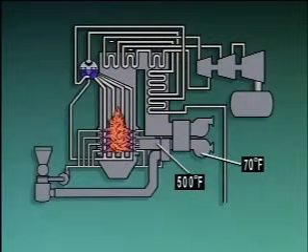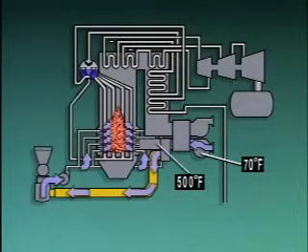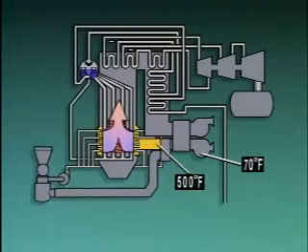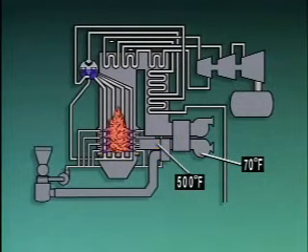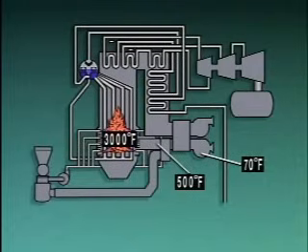After passing through the air preheater, the heated air is split into a primary air supply and a secondary air supply. The primary air flows to the pulverizer, where it's used to dry pulverized coal and carry it to the burners. The secondary air flows to the burners, where it rejoins the primary air and helps to support combustion. When the fuel and air mixture is ignited in the burners, the flame burns at approximately 3,000 degrees Fahrenheit.